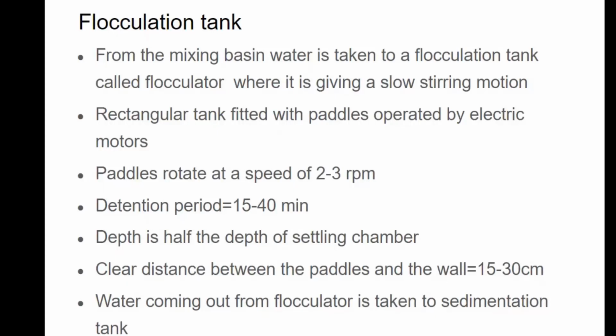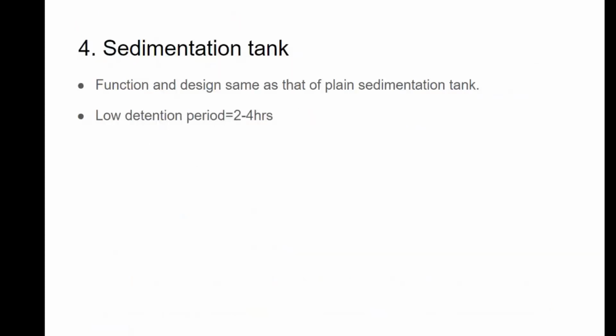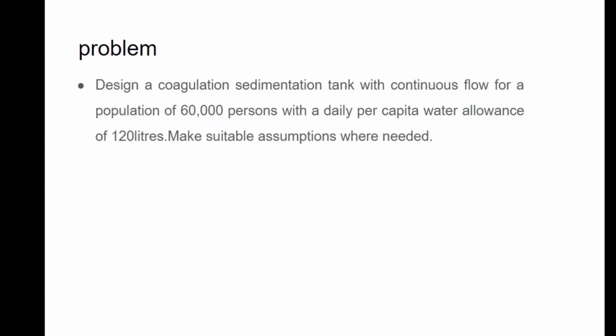Clear distance between the paddles and the wall will be 15 to 30 centimeter. Water coming out from the flocculator is taken to the sedimentation tank. Then the sedimentation tank: function and design are the same as that of the plain sedimentation tank. And a low detention period is given to the sedimentation tank, that is 2 to 4 hours.